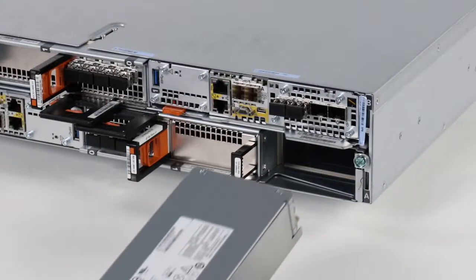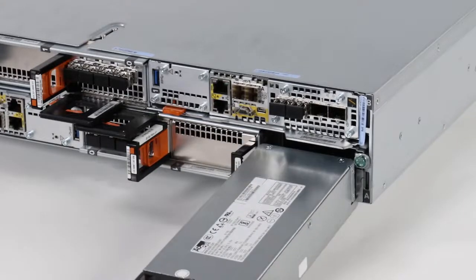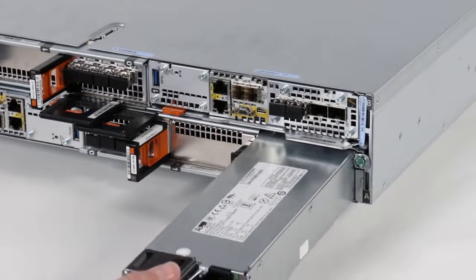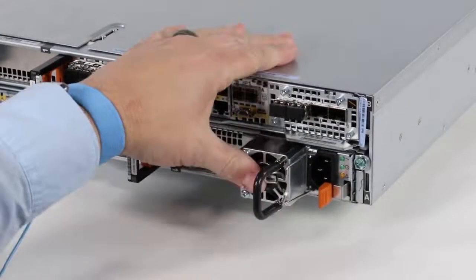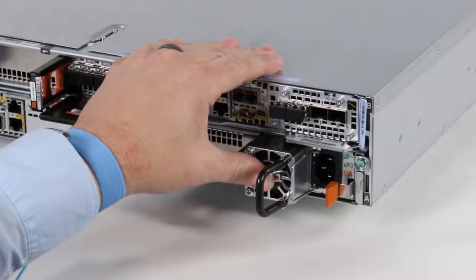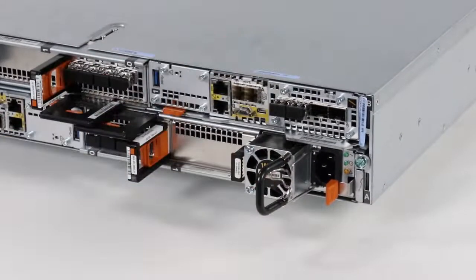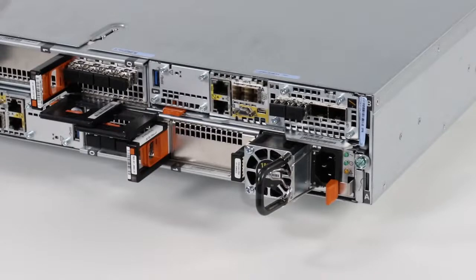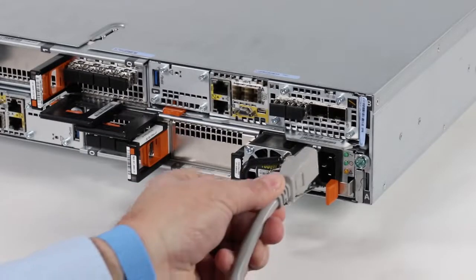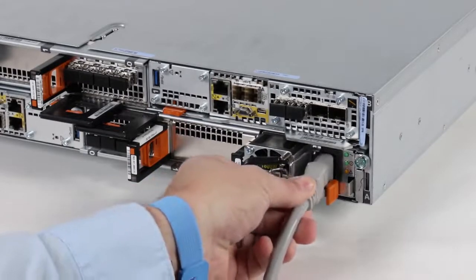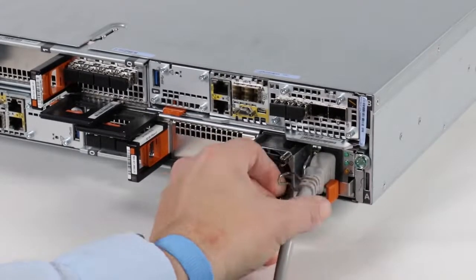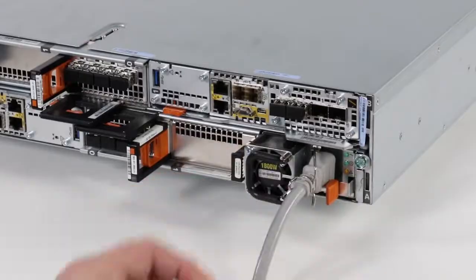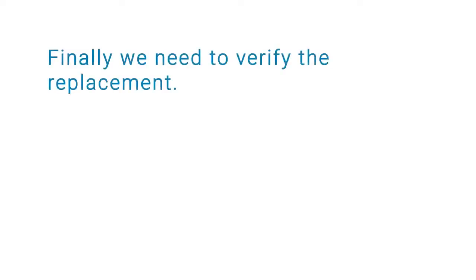Now, install the replacement power supply. Align the power supply with the slots in the node. Push the power supply into the node until it clicks into place. Next, connect the power cable to the power supply and secure the cord with the retention bail.